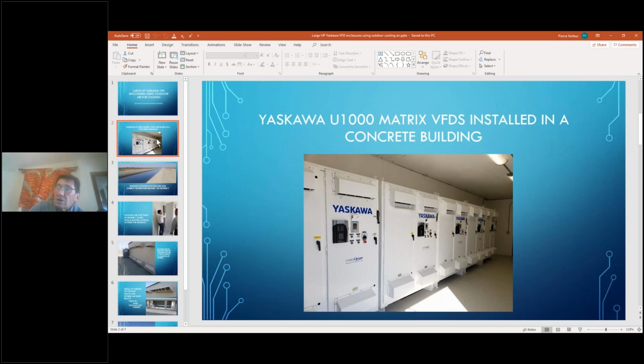Those are to provide airflow over the circuit boards and the thermal energy being exhausted from the upper port, because we always at Yaskawa put fans at the top, filters at the bottom, and suck air up through the system. The reason for that is that it follows the natural convection, so we're not fighting the natural convection. And we have lowered air inlet velocity at the inlet, so we don't suck up as much dust. We don't make a Hoover vacuum cleaner.